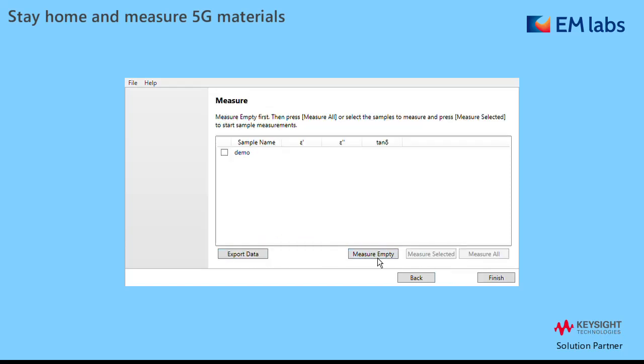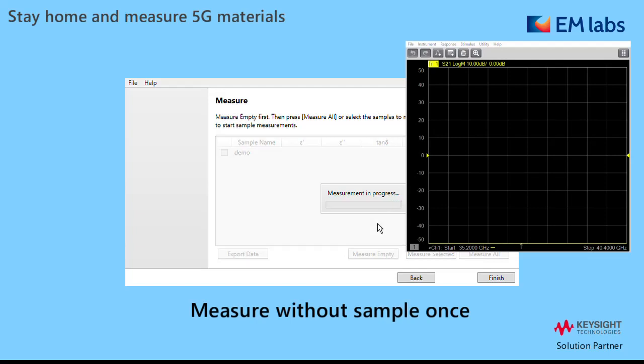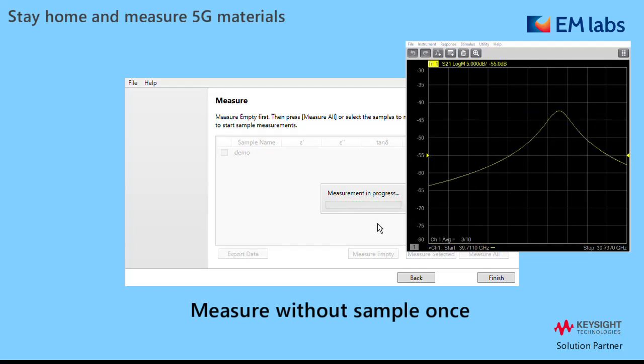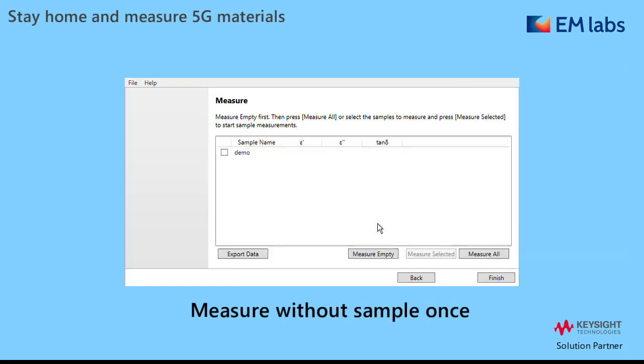As a final step of the setup, characterize the resonator without a sample. This step is necessary only once in a series of sample measurements because the resonator is very stable.